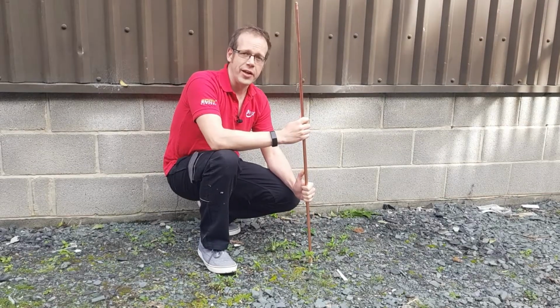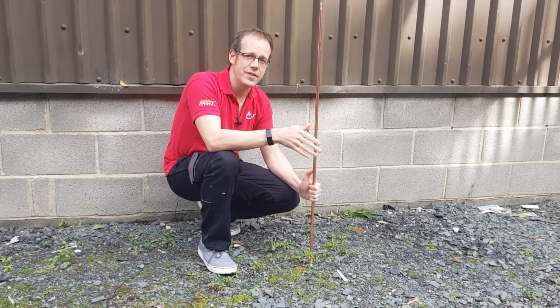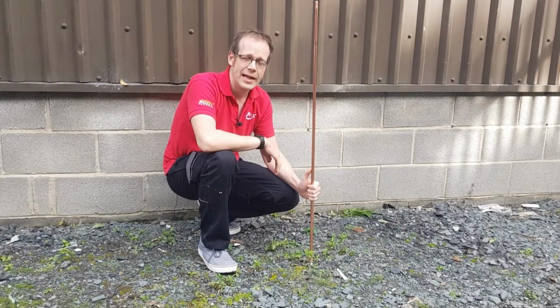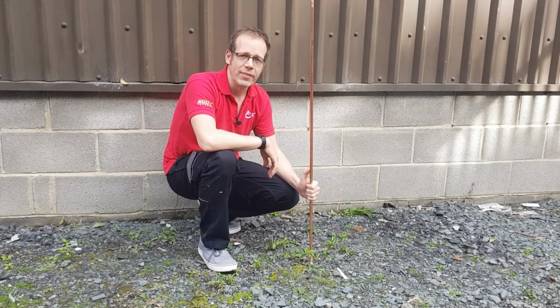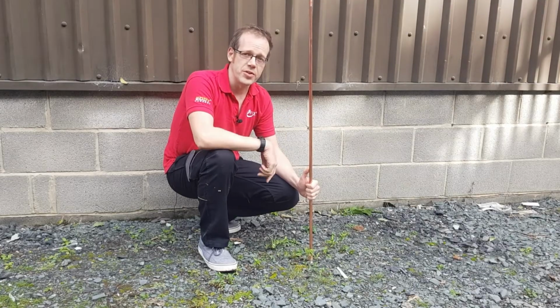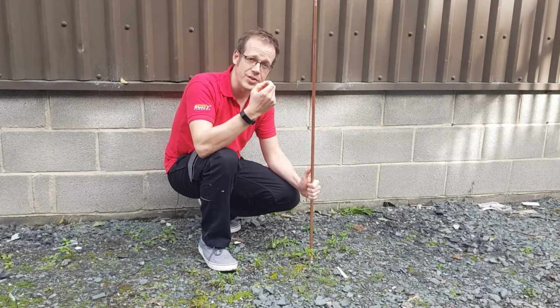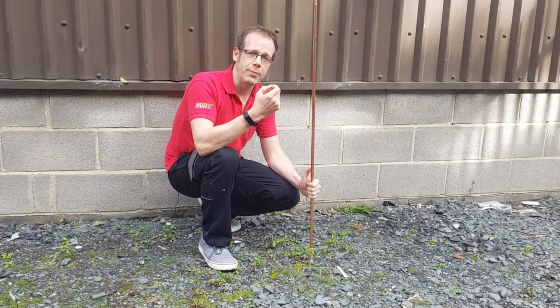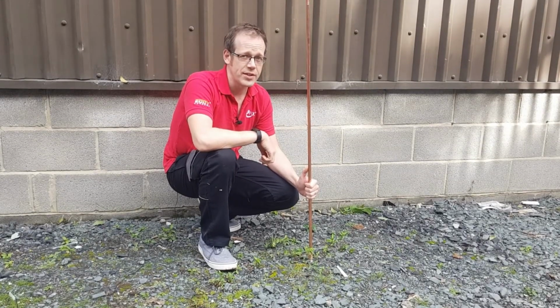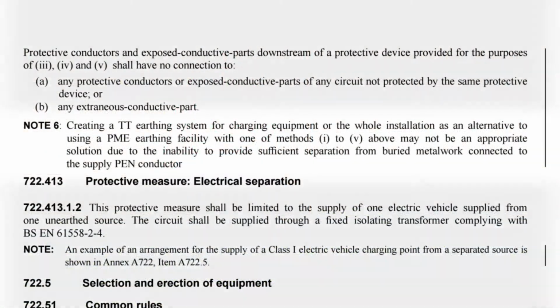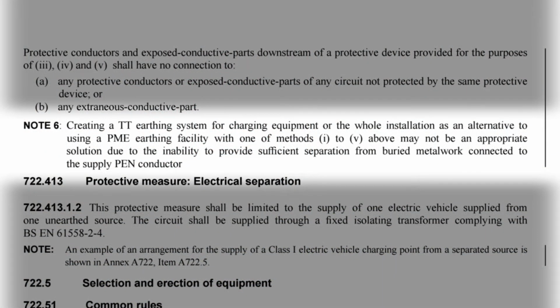However, hammering an earth electrode into the ground is fraught with hazards from hidden services such as gas, water and electricity supplies, and achieving a low enough resistance is also challenging. So BS 7671 allows for some other options instead, and indeed it was the proliferation of solutions to this very problem that triggered the issuing of Amendment 1. And Amendment 1 contains this interesting point in Note 6, where we read: creating a TT earthing system for charging equipment or the whole installation as an alternative to using a PME earthing facility with one of methods 1 to 5 above may not be an appropriate solution due to the inability to provide sufficient separation from buried metalwork connected to the supply PEN conductor.